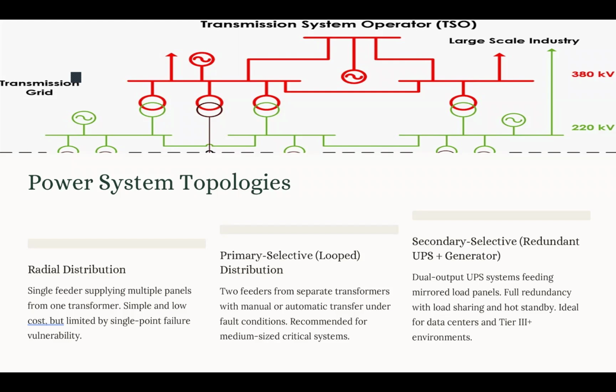The advantage of this topology is that it improves the reliability compared to the radial distribution, and we have fault isolation possible with minimal downtime. There are some disadvantages to that topology. One is that it doesn't have an instantaneous power transfer unless it is fully automated. It is more expensive compared to the radial distribution because it needs extra feeders and a transfer mechanism. So we need to choose. It is a trade-off, basically, if you want to choose between the radial distribution and primary selective distribution.